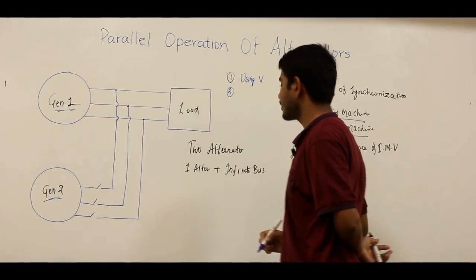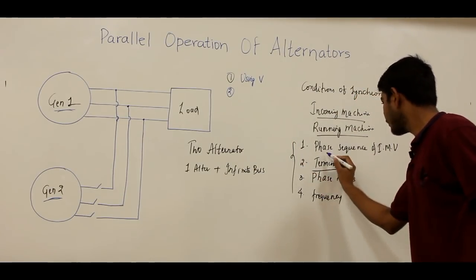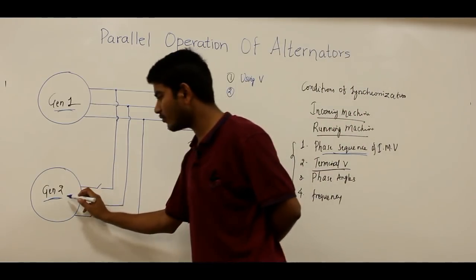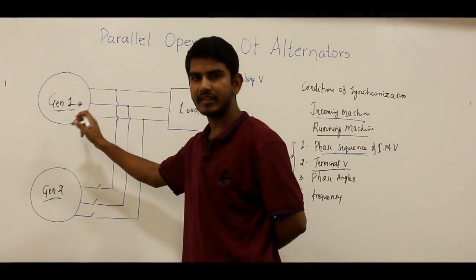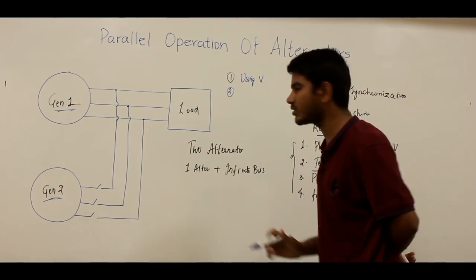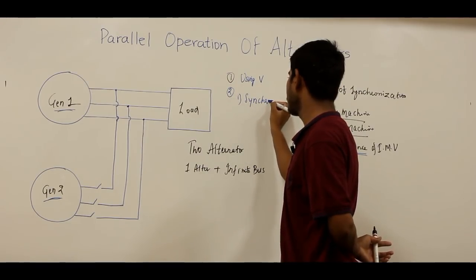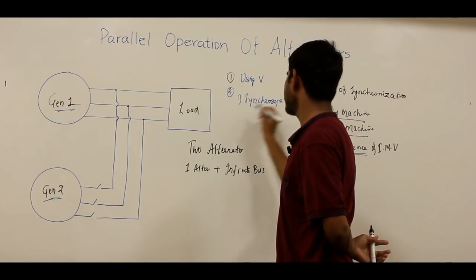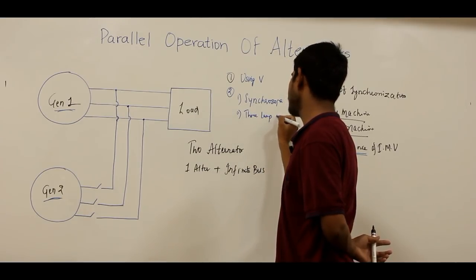The second thing to check and verify is the phase sequence. The phase sequence of the incoming machine voltage should be equal to that of the running machine. There are two methods to check phase sequence: the first is by using a synchroscope, and the second is the three lamp method.